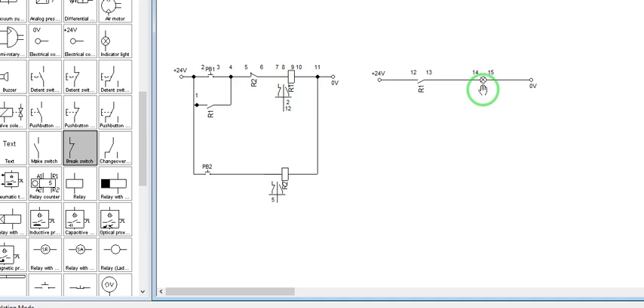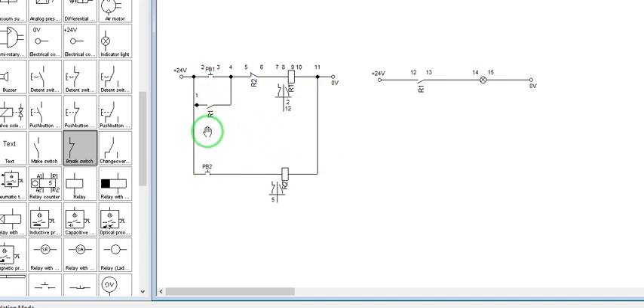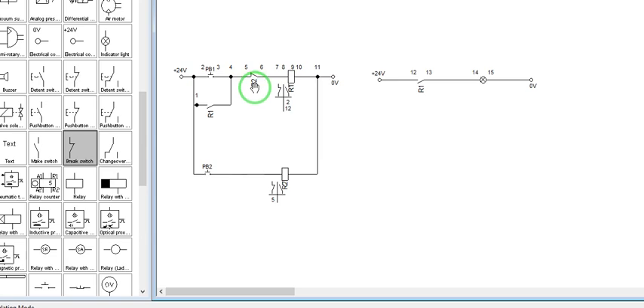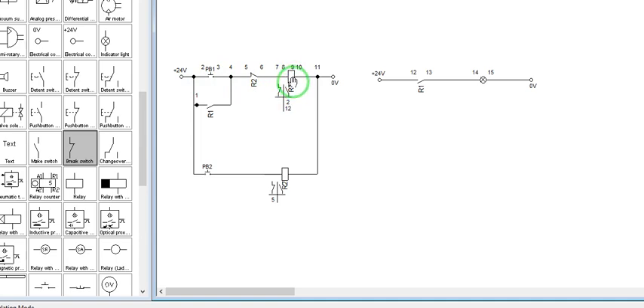Now, why do we call this a reset priority? We call this a reset priority because if you press both push buttons at the same time, Relay R1 will always be reset — that is, Relay R1 will always be de-energized. If we press Push Button 2, relay contact R2, which is normally closed, will always open. So even if you press Push Button 1, it can never have a complete path going to Relay R1, so R1 will never be energized or set. Therefore, if both push buttons are pressed, R1 will always be reset or de-energized.